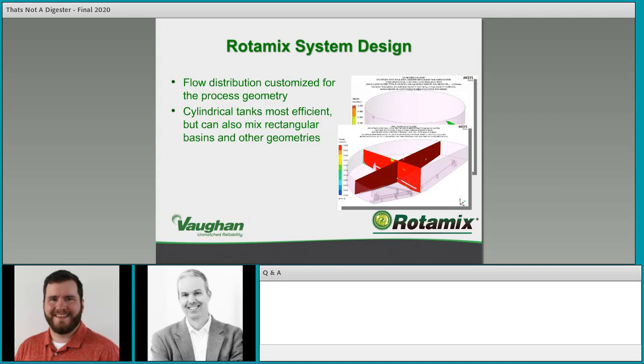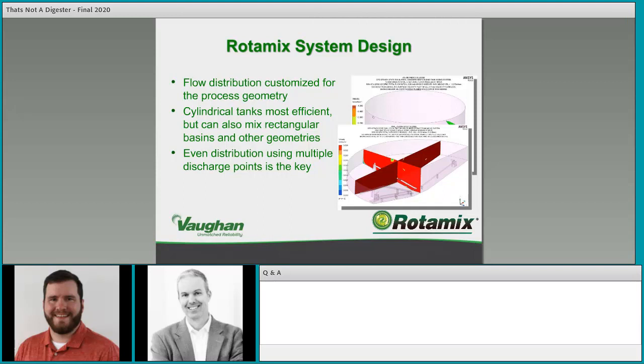That was a very challenging geometry to provide consistent mixing across the entire volume, but it's something we're able to design for. It took quite a bit of work and revision to make sure the mixing system met the needs of the process. The key is even distribution of mixing through multiple discharge points — taking a single momentum source through the pump and driving it through various nozzles located in different areas to distribute that energy and drive the bulk mass flow.